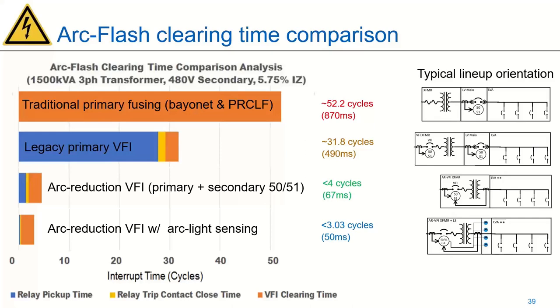So in a system with an NGR, you might want a lower ratio neutral CT, because you're going to want to pick that up more sensitively, versus a solidly grounded system, where you're going to see the full brunt of fault current. So that is something that is important, but it can absolutely be tailored with this type of protection, most definitely.